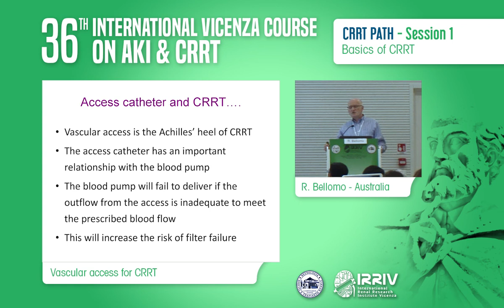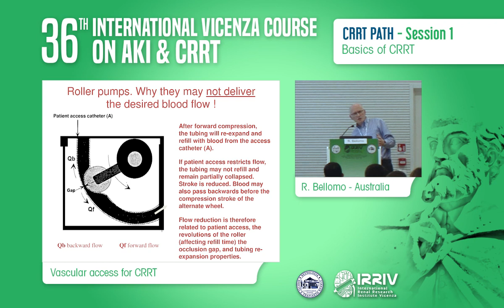It has very important relationships with blood flow through the circuit, with the way the blood pump is able to deliver the prescribed blood flow, and the risk of filter failure that emanates from that. I wanted to show you this diagram because maybe some of you don't quite think about why the blood goes from the vein into the circuit and how a peristaltic pump works. A peristaltic pump compresses the tubing of the circuit, and as it rotates, it creates a suction effect by squashing the tubing and then allowing it to expand. As the tubing expands, it creates a negative pressure, and it makes the blood flow from the vein into the tubing. The tubing gets filled up again, and then the next rotation of the cam moves it forward.